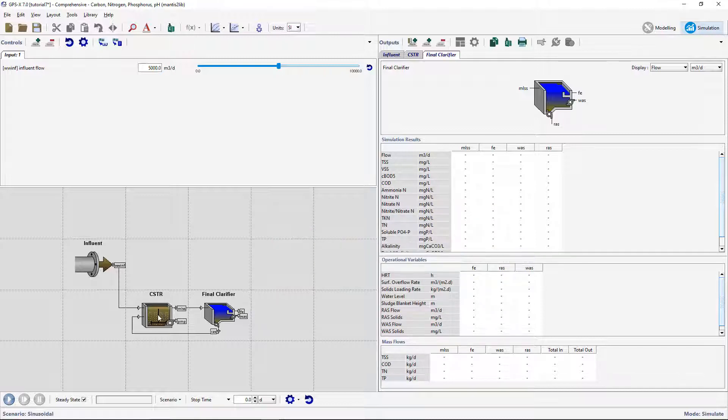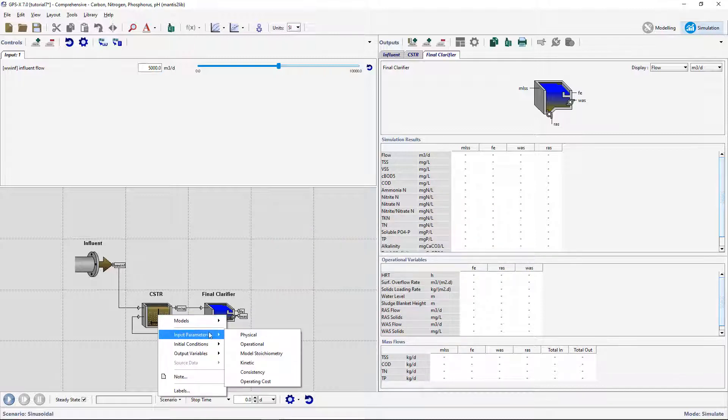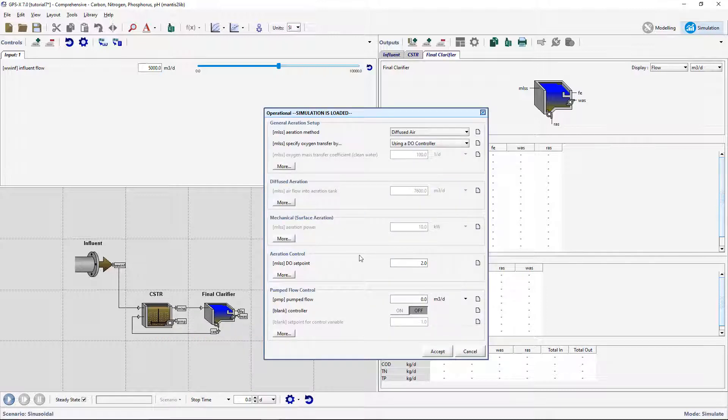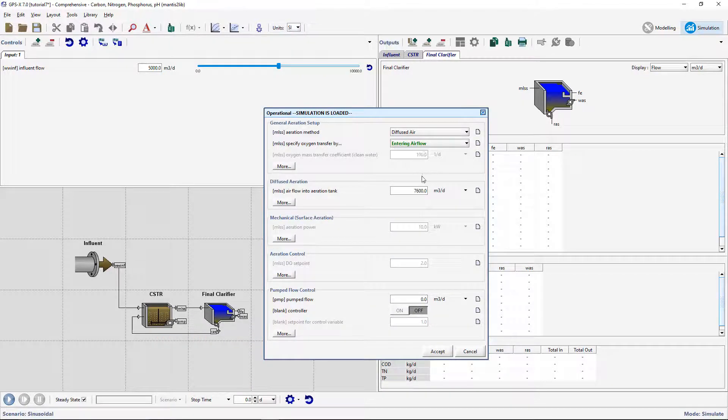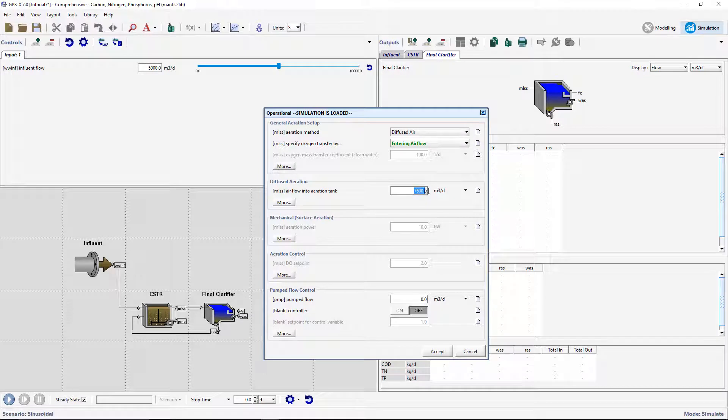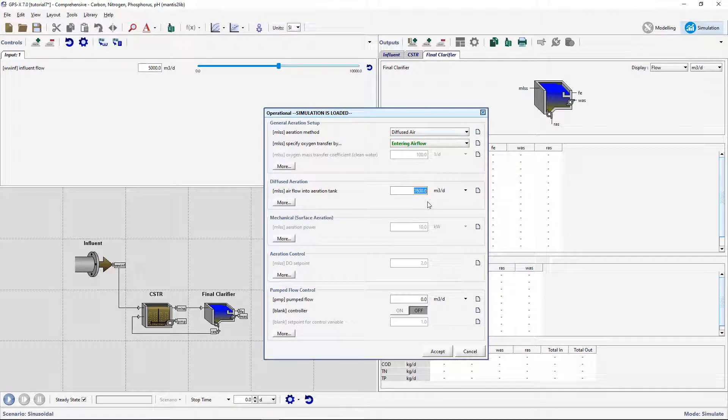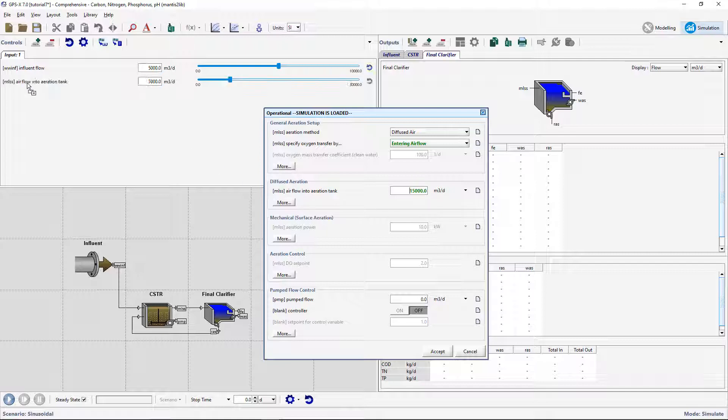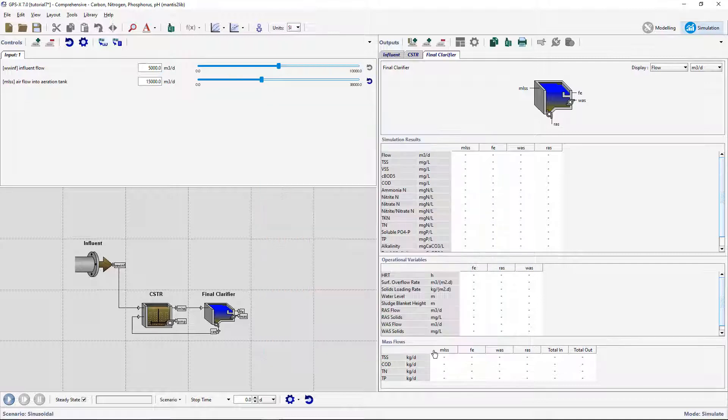Right-click on the CSTR and go to Input Parameters, Operational, and change the Specify Oxygen Transfer by selection to entering Airflow. Set the airflow into the Aeration Tank to 15,000 m3 per day. Drag the airflow into Aeration Tank variable to the Input Controls section.